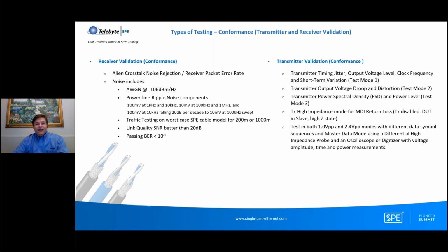And then finally, we have a MDI, a medium dependent interface return loss measurement, where we want to see how closely the devices match the 100 ohm differential characteristic impedance. So the cable is 100 ohms. We're trying to match, for maximum power transfer, the impedance of the devices together. So the input impedance matches the output impedance of the devices. We have to test these in both 1 volt and 2.4 volt peak-to-peak modes, and use different data sequences with a differential high impedance probe and either an oscilloscope or a digitizer to monitor the transmit signals.